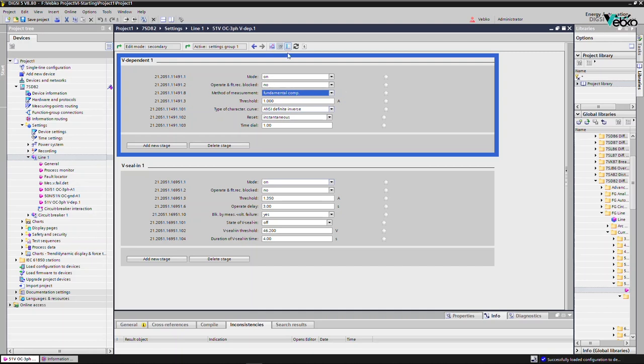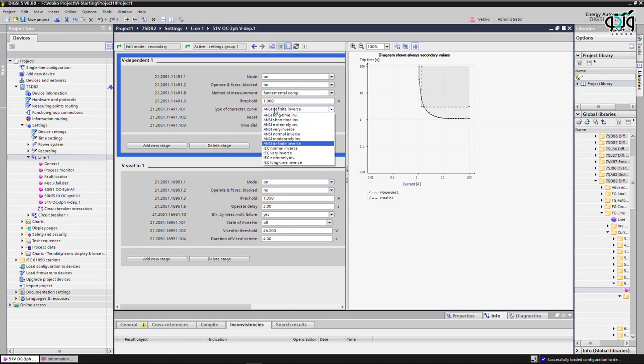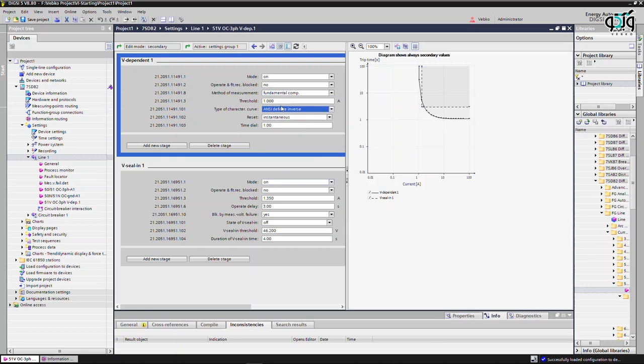The 1.5 ampere current setting value is also a good option for most applications. The current threshold parameter for lines is up to 10% and for transformers and motors up to about 20% higher than the maximum expected load. In the characteristics section, select the curve according to IEC and ANSI standards. Here, the 1 ampere setting is used.